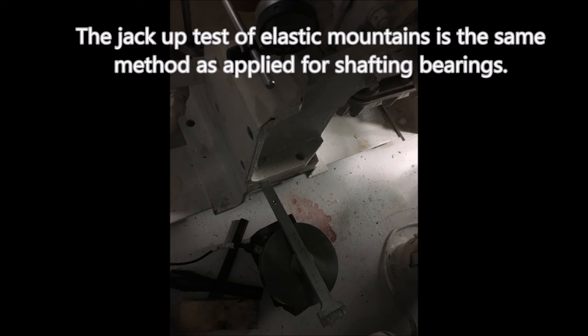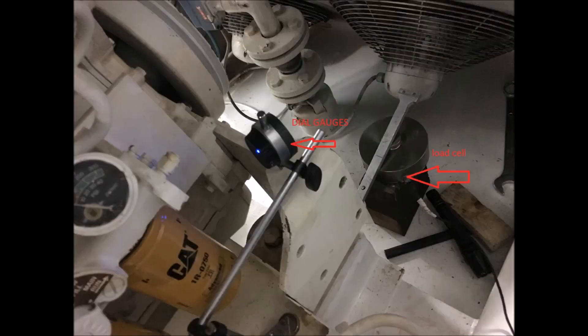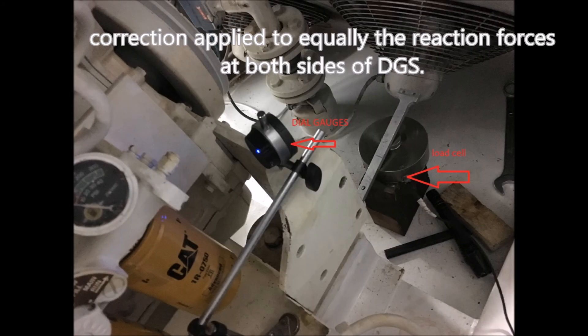The jack-up test of elastic mountings is the same method as applied for shafting bearings. Correction is applied to equalize the reaction forces at both sides of DGS.